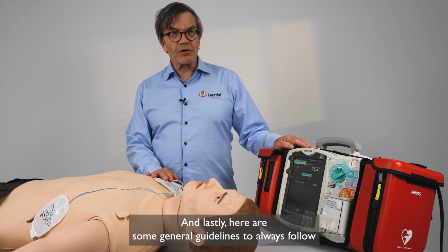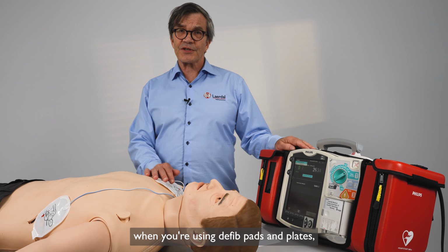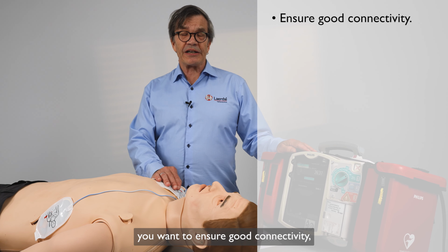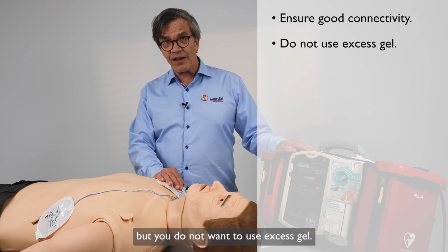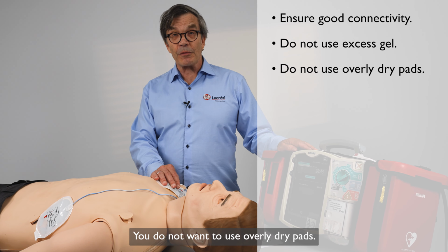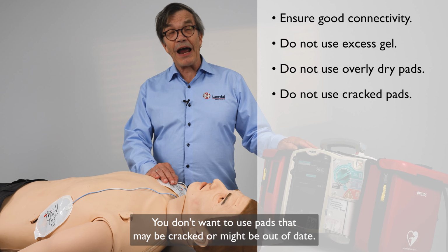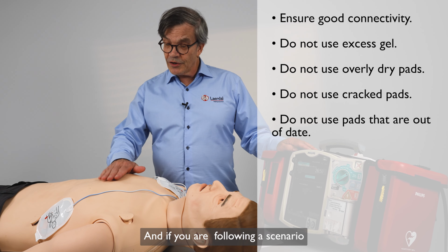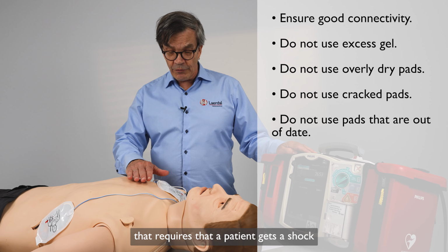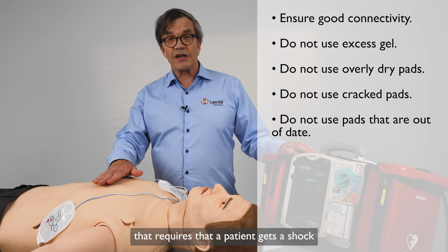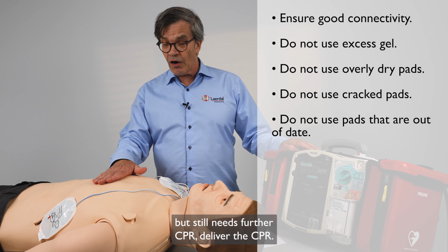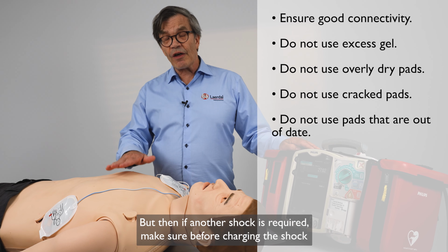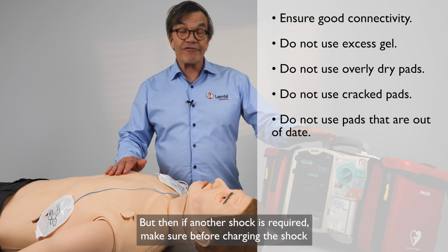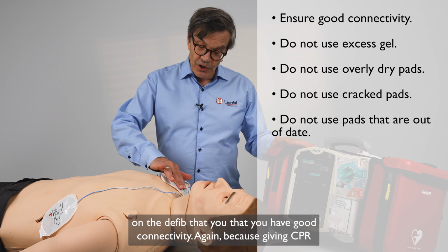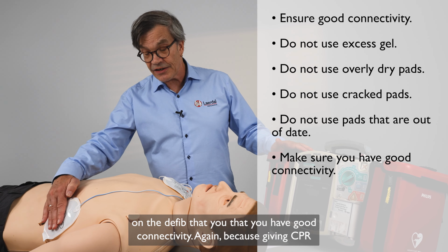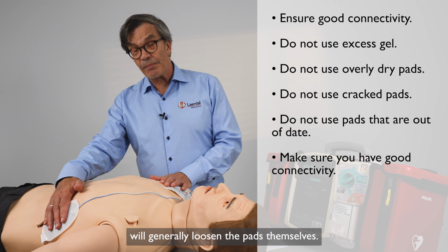And lastly, here are some general guidelines to always follow when you're using defib pads and plates. You want to ensure good connectivity, but you do not want to use excess gel. You do not want to use overly dry pads either. You don't want to use pads that may be cracked or might be out of date. And if you're following a scenario that requires that a patient gets a shock but still needs further CPR, deliver the CPR, but then if another shock is required, make sure before charging the shock on the defib that you have good connectivity again, because giving CPR will generally loosen the pads themselves.